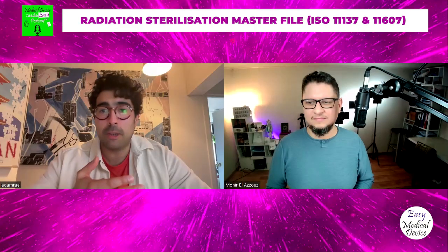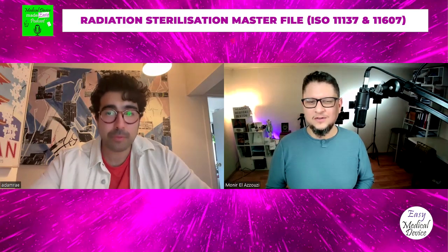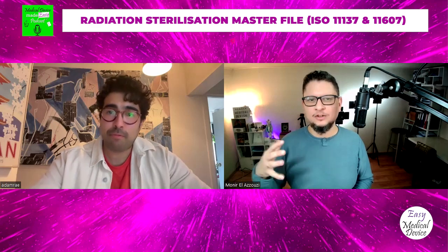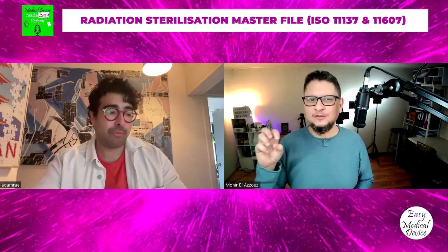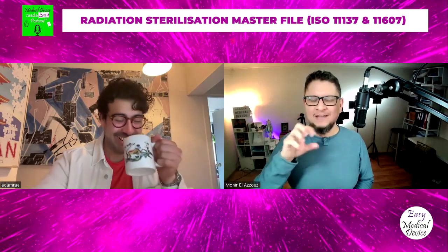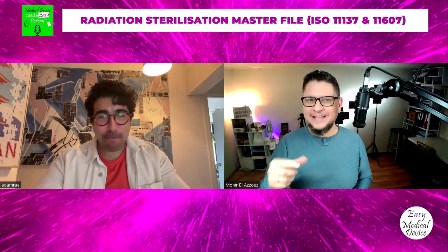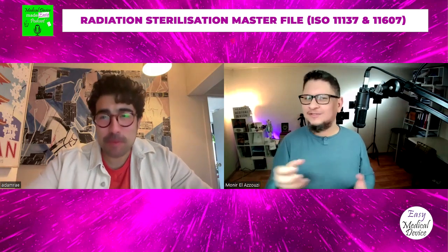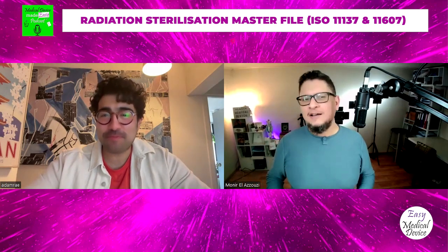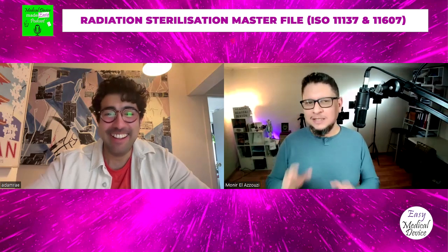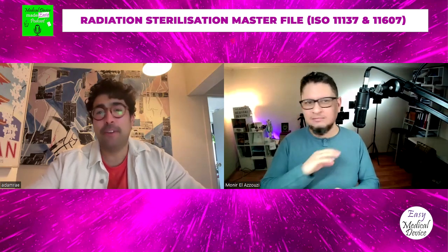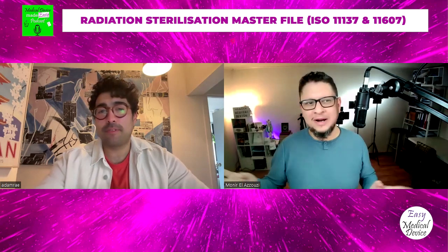Because as soon as you put it in a technical document, it can be subject to further review. So I'd say any piece of equipment that they mention, calibration data. Yeah, so it's funny because I'm auditing a lot of companies, and this is my low-hanging fruit. When I visit the manufacturing plant, I visit each step, and I look at each instrument that they are using for calibration. I look at the date on it, etc., because I say I will find for sure something that was not calibrated. Sometimes I have some companies that are really great and work really well, and I was searching everywhere, I can't find anything.